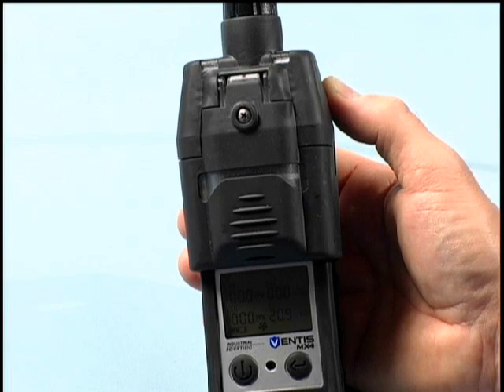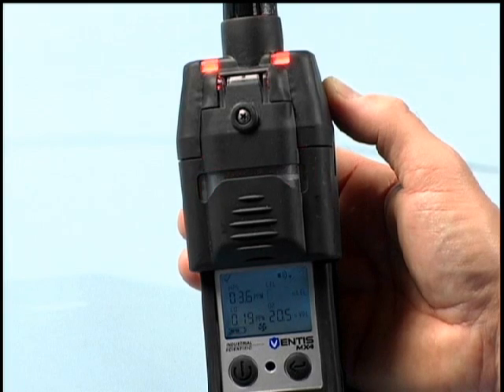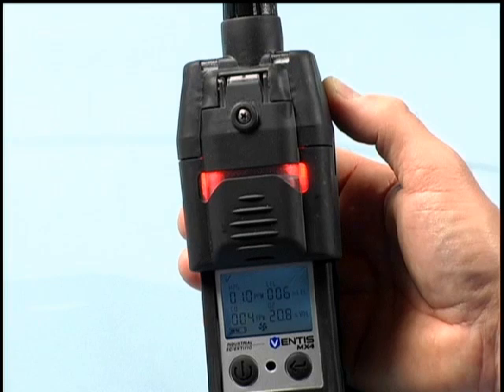The Ventis MX4 comes standard equipped with audible, vibrating and visual alarms. These alarms are designed to alert the user of escalating gas conditions. There are both a low and high alarm for each installed sensor. The low alarm is signified by a pulsed tone, vibrating pulses and corresponding LED activation that can be viewed from the front, side and top of the instrument.